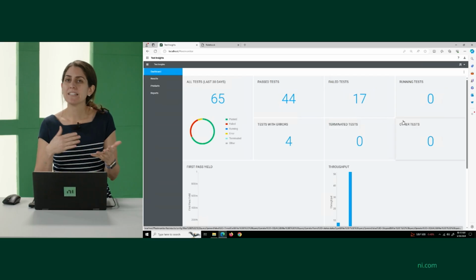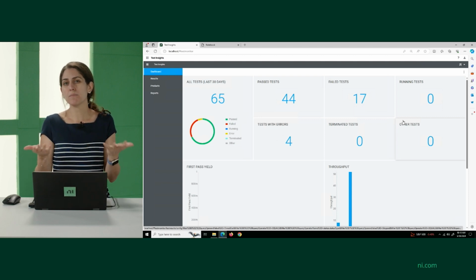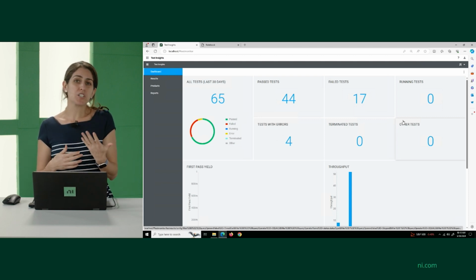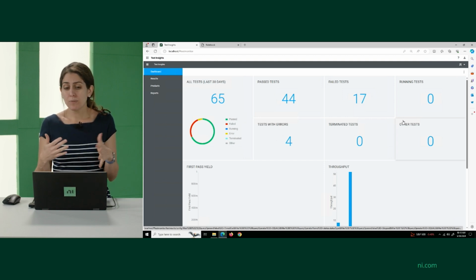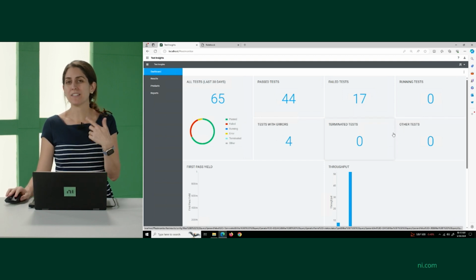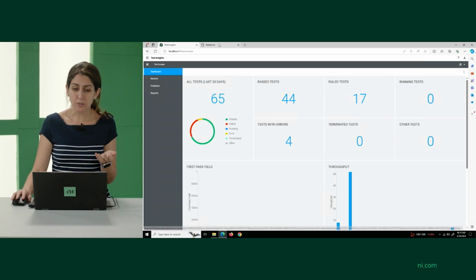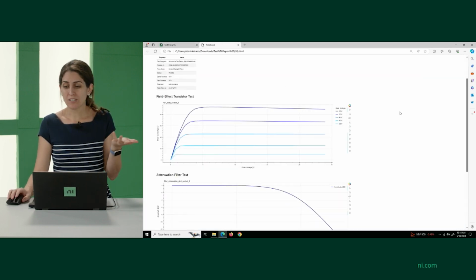So one last thing I'd like to quickly talk about is data management and analysis. You can customize TestStand reports to share results and the data on the actual devices under test. But if you're looking to understand how your actual tests are performing, not just how the DUTs are performing, this system also hooks up into asset and data management programs like SystemLink. For example, here we're using SystemLink Server, so you can monitor and manage the system from anywhere, deploy new versions of the tests remotely, and we've even created a task that gets triggered whenever this test runs to create a custom report right here that we've written in Jupyter and Python.